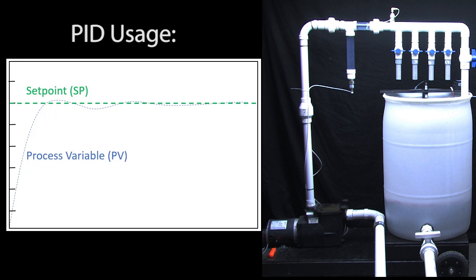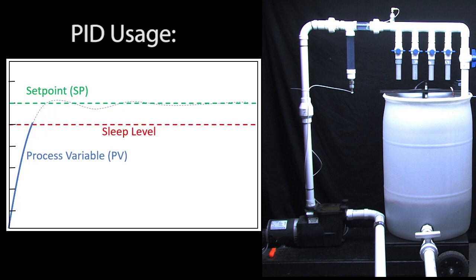That is, when sleep mode enables the frequency output to the motor, PID will see that the water level is way off and it will automatically try to get the water level back to the set point as quickly and efficiently as possible. But sleep mode is going to cut the motor off before it gets there. So we're just using the PID function to automatically control the motor speed while filling the tank.